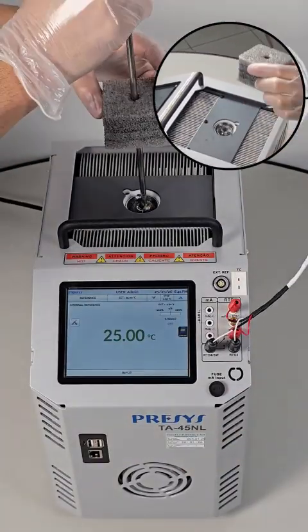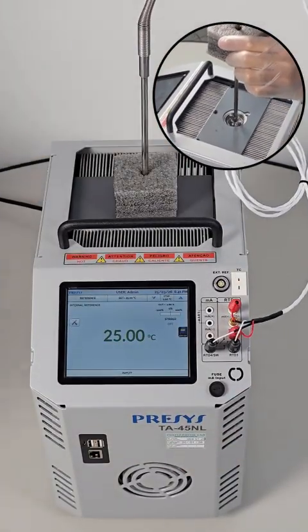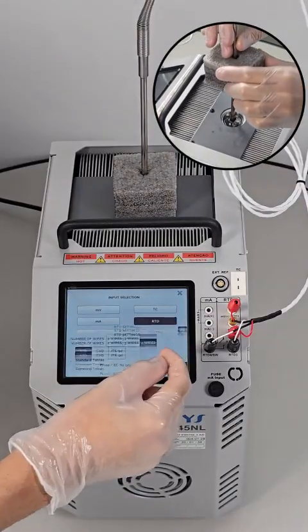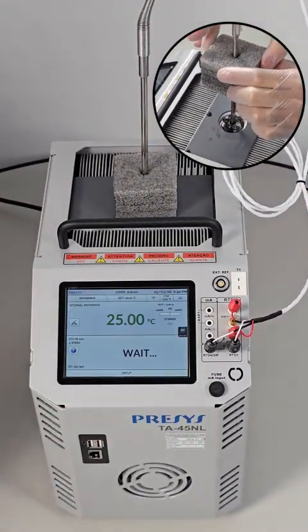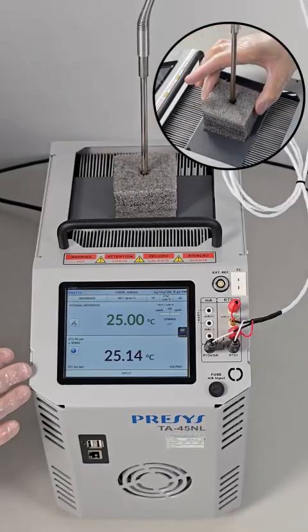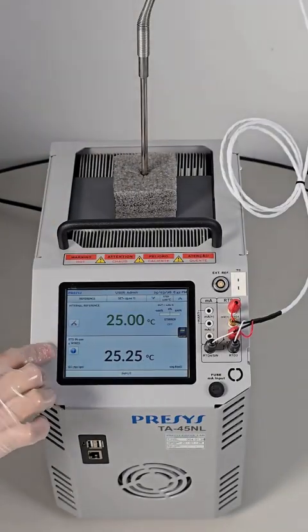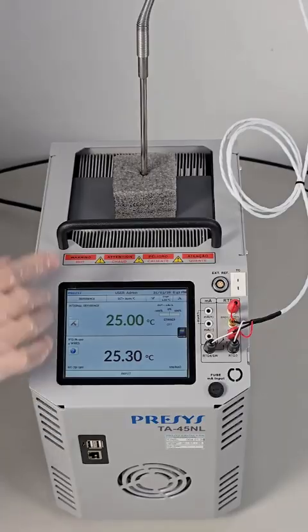Insert the monitoring sensor into the well of the cell. This sensor will measure the internal temperature of the cell, not the bath temperature, which is essential due to the significantly higher thermal inertia of the water mass.